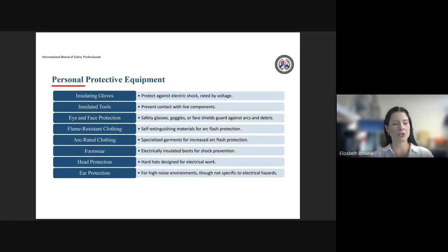Okay, so with OSHA and with any type of safety management, we want to consider personal protective equipment for employees, but we want to consider it as a last resort. The main reason for that is because personal protective equipment is not preventing the hazard from happening. It's not preventing an employee from being exposed to electrical current. It's just trying to protect them from it. So we want to use engineering controls. We want to use work practice controls. And we want to use personal protective equipment only after we have exhausted the potential of using those other more effective controls.